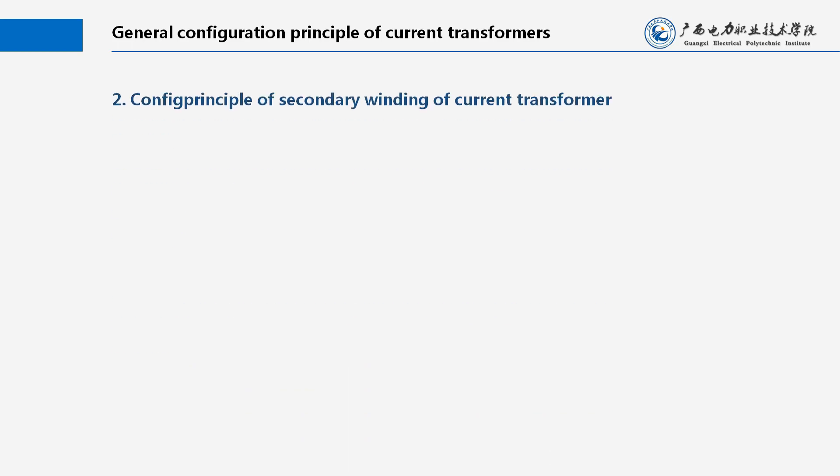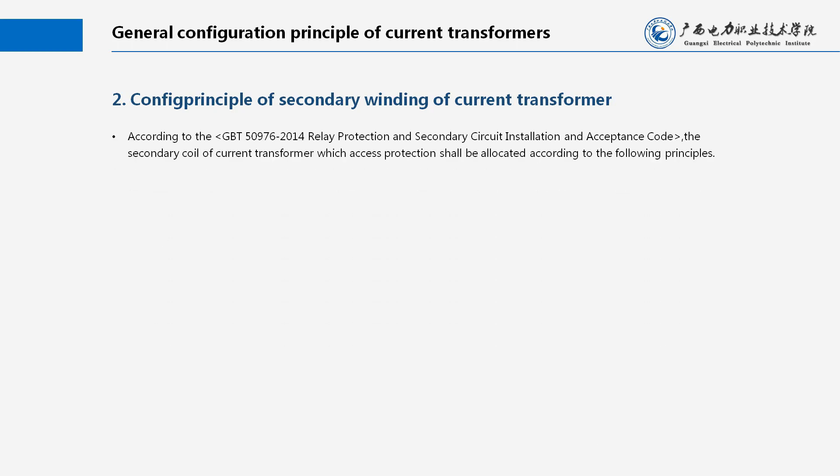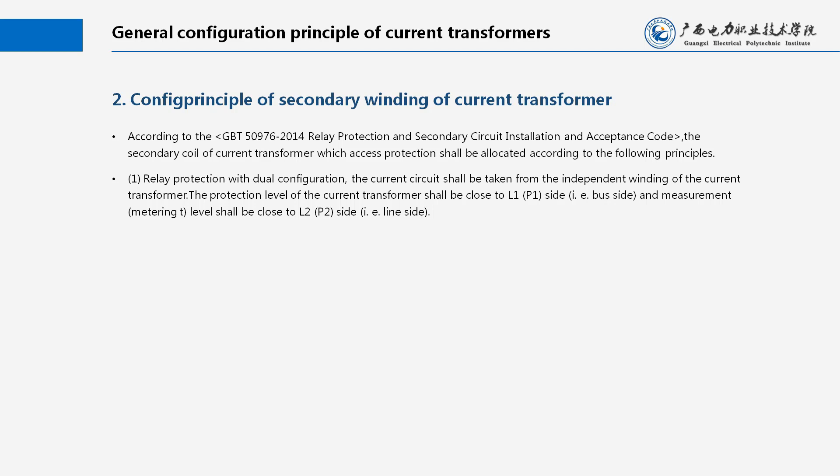Configuration Principle of Secondary Winding of Current Transformer: According to the GBT-50976-2014 Relay Protection and Secondary Circuit Installation and Acceptance Code, the secondary coil of the current transformer which accesses protection shall be allocated according to the following principles. 1. Relay protection with dual configuration: the current circuit shall be taken from the independent winding of the current transformer. The protection level of the current transformer shall be close to the L1, P1 side (i.e. bus side), and measurement and metering level shall be close to the L2, P2 side (i.e. line side).